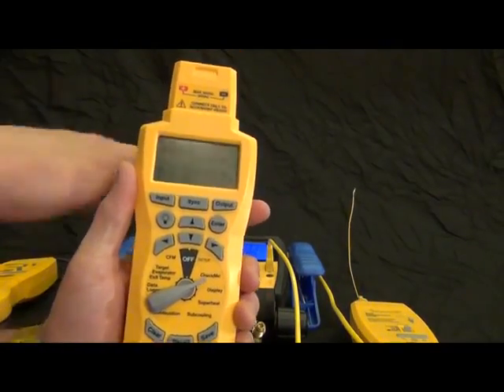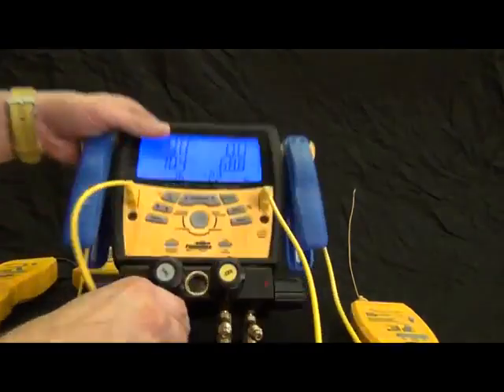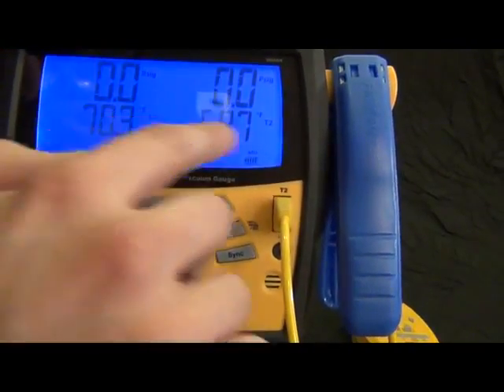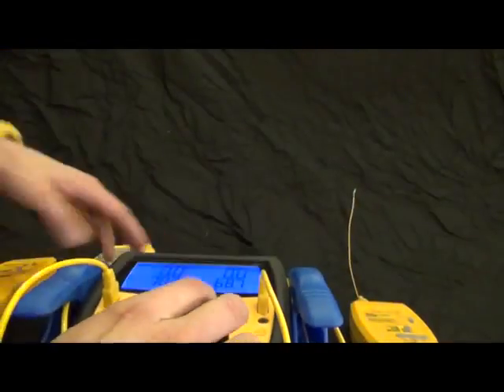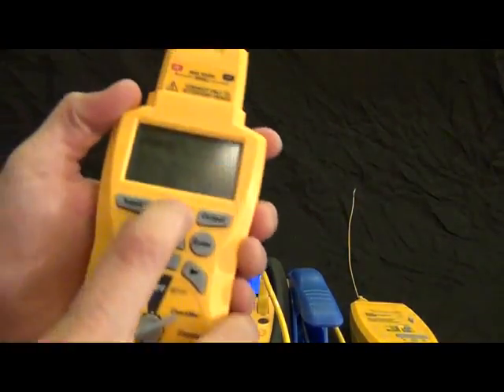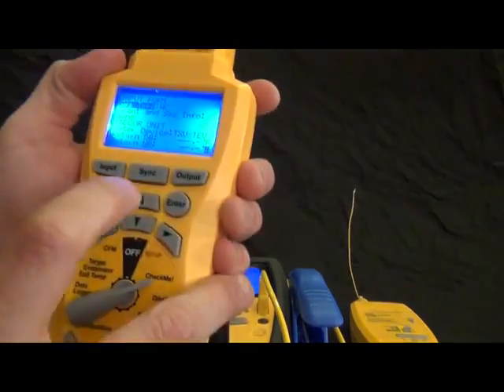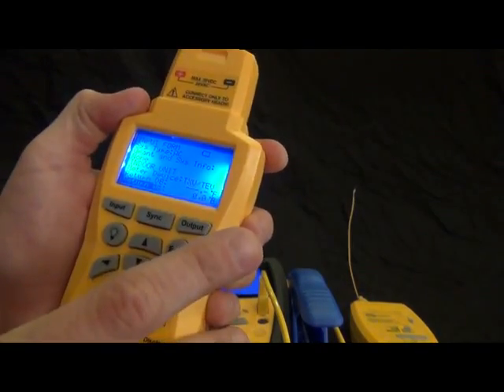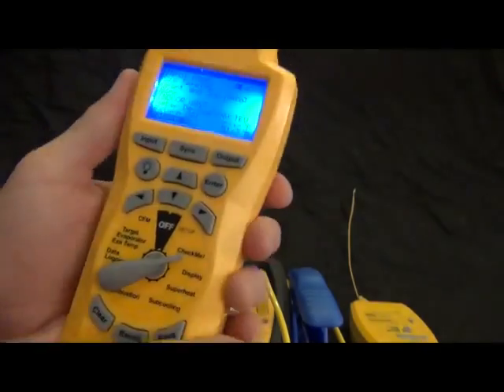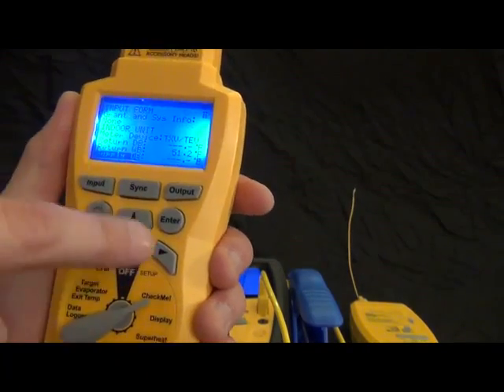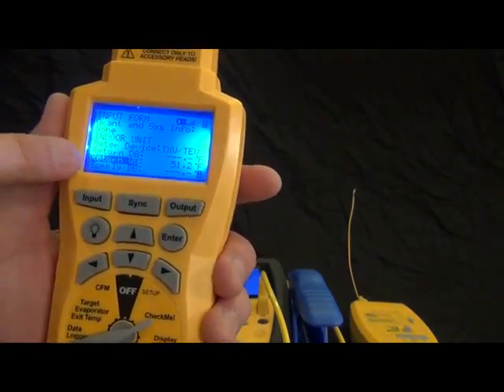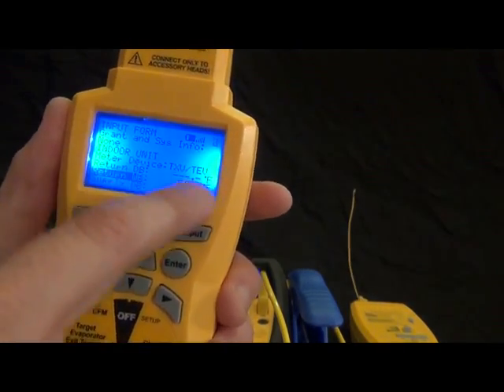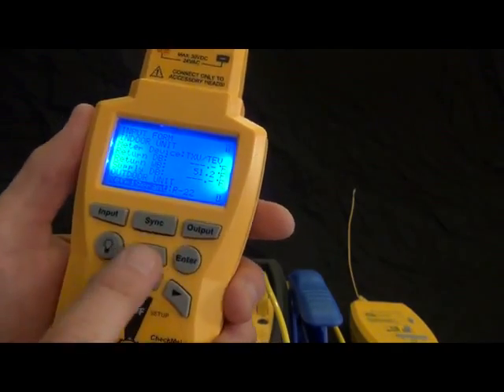So how I do that is I just put it in T1 and T2 direct mode on the S-Man 4 and you know that by the T1 and T2 and I just hold down sync and then now it's waiting for the HG3 to get synced and I just hold sync on the HG3. And there we go. Actually before you press sync what you want to do is highlight one of the measurements that the S-Man 4 is sending. So I highlighted return wet bulb and it knows to sync the return wet bulb. It will also sync the other five measurements.